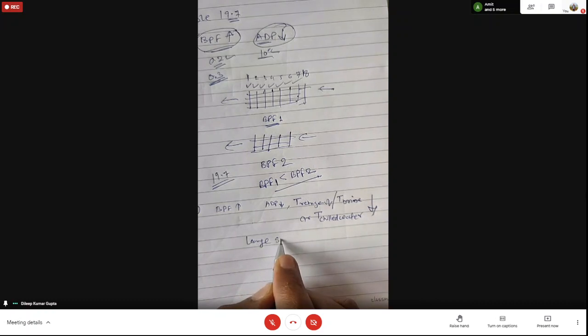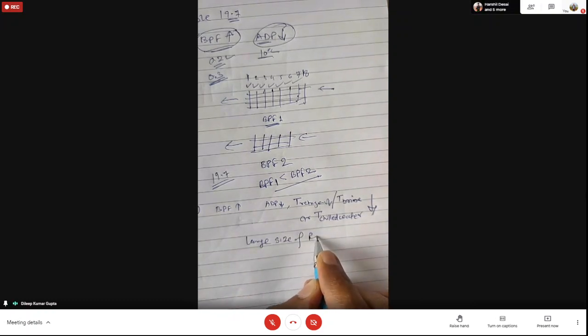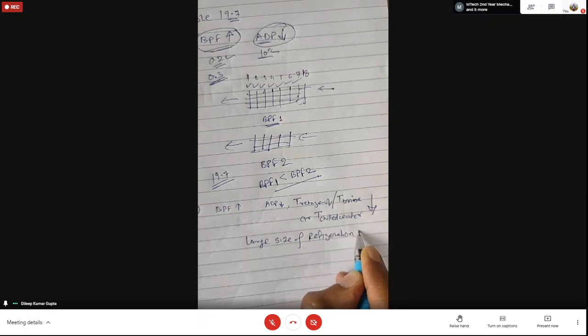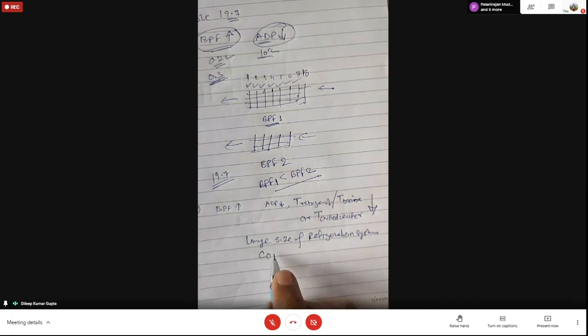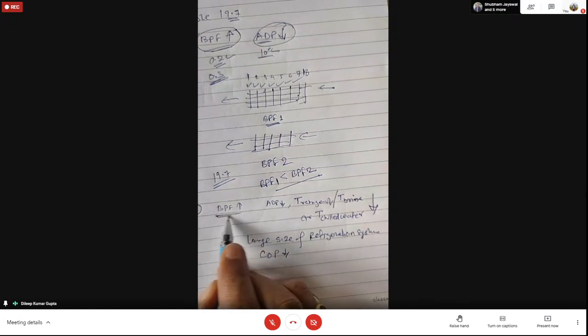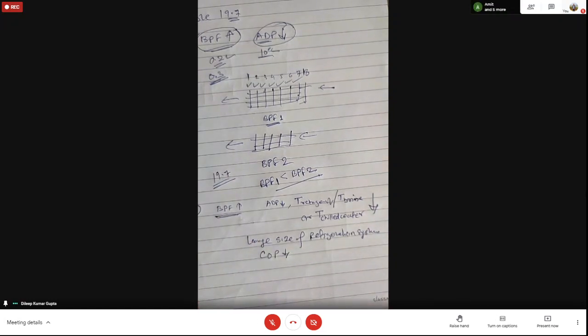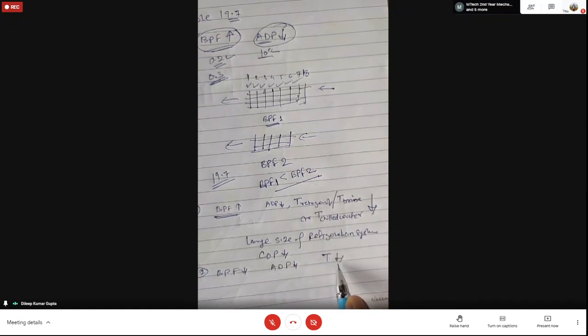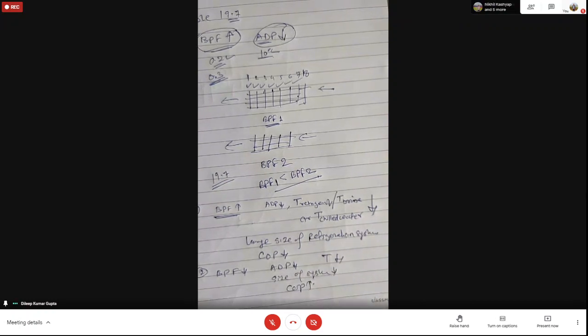Large size of refrigeration system required. A large coil required, sorry, large refrigeration system required for this one, and the value of COP is going to decrease. These are the effects of increasing the bypass factor. Just opposite of that, second case, bypass factor is lower. If bypass factor is lower, ADP will be higher. If ADP is higher, these temperatures will be higher, and this temperature will be higher, then the size of the refrigeration system is going to reduce, and finally COP will be higher. These are the effects.